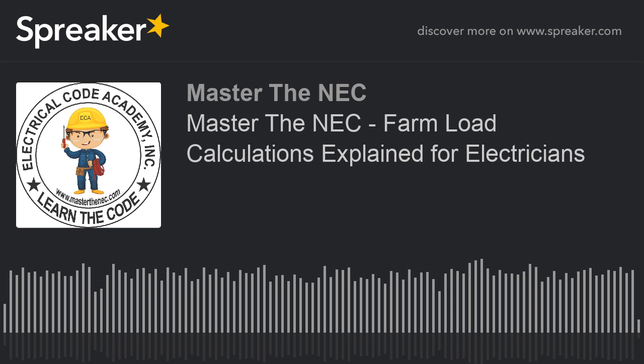So what are the remaining loads? The remaining loads are all those assorted loads that we talked about in the explanation, which was 92 amps. So you take those remaining loads at 50%. Those remaining loads could be anything from small branch circuits to something else on the farm, a little smaller motor or whatever it may be. We're applying demand factors here, and if motors are similar we can add them together. This was 92 amps of remaining load, and we do it at 50%, that's 46 amps.